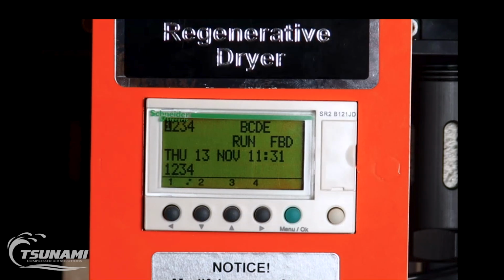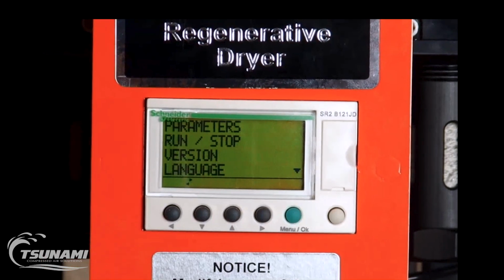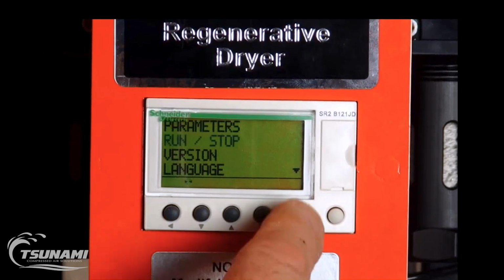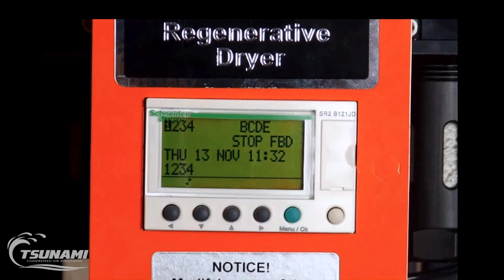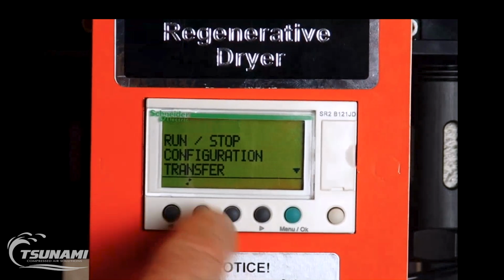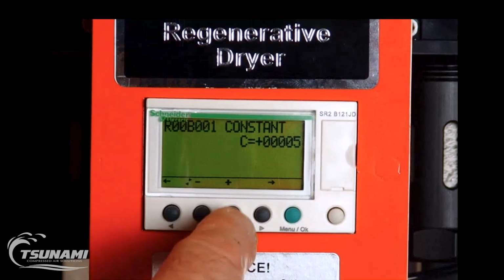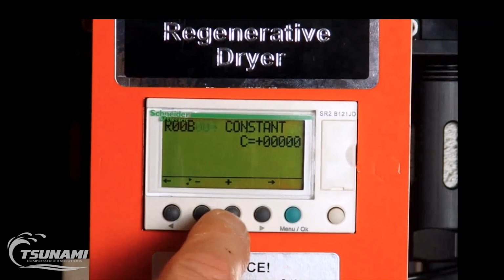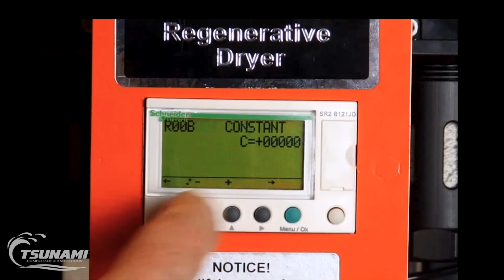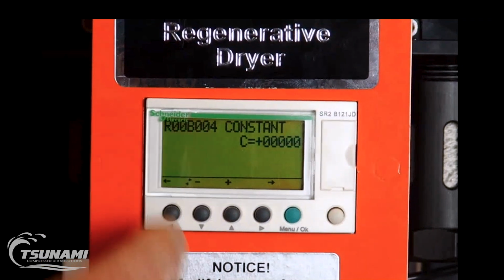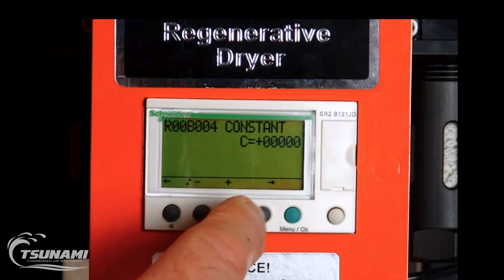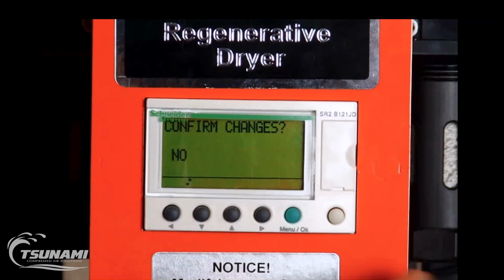So what we're going to do to turn this on when this input signal is coming in is change that parameter. We will go down and stop the program. Then, following the instructions, you would go into the parameters. We will scroll the block value, and we want to go to block 4. We're going to hit the right arrow over and change that constant value to a plus 00001. We're going to confirm that change.